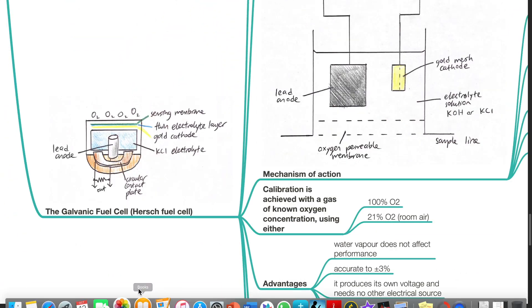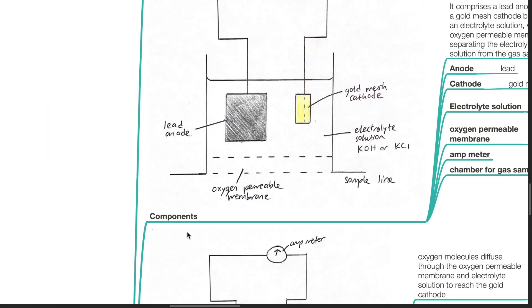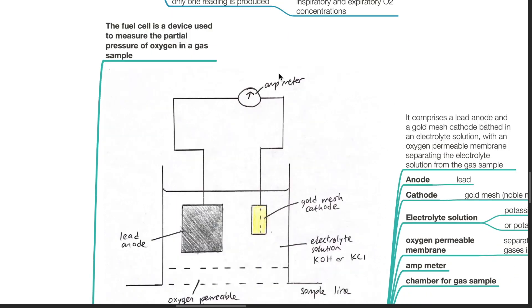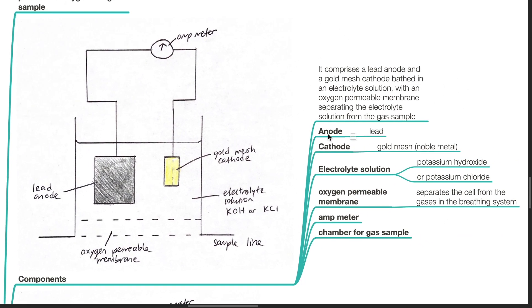The galvanic fuel cell, or Hersch fuel cell, is a device used to measure the partial pressure of oxygen in a gas sample. Components include an anode made of lead, a gold mesh cathode, and an electrolyte solution of either potassium hydroxide or potassium chloride. An oxygen-permeable membrane separates the cell from the gases in the breathing system, along with an ammeter and a chamber for gas sample.